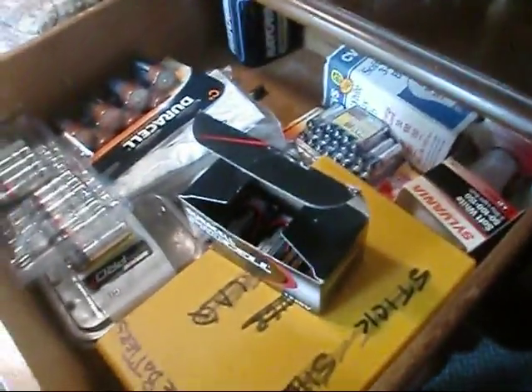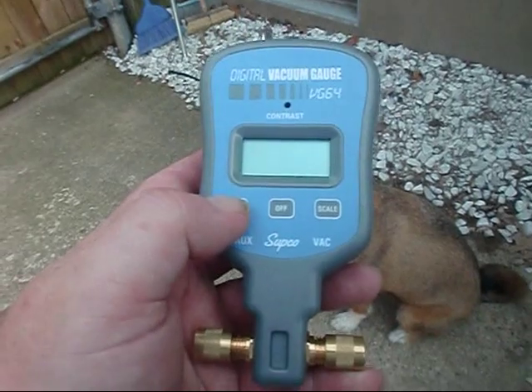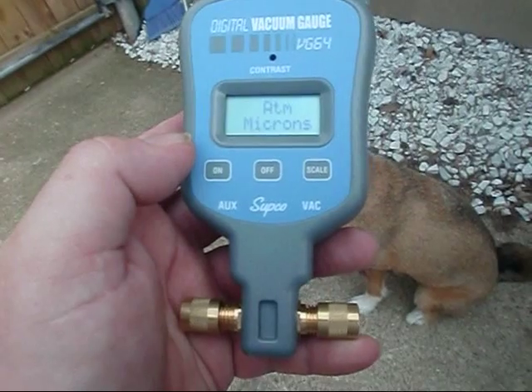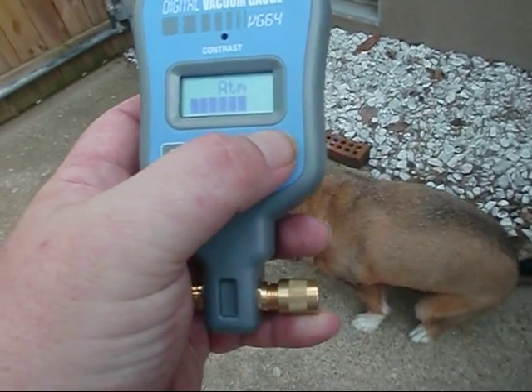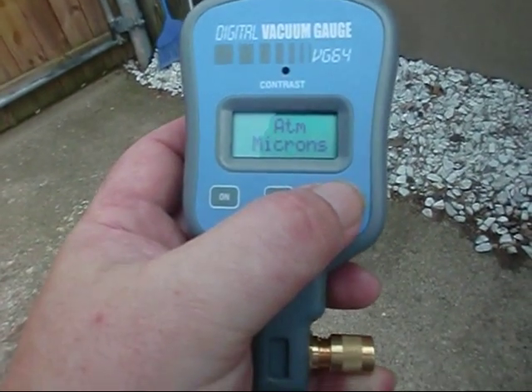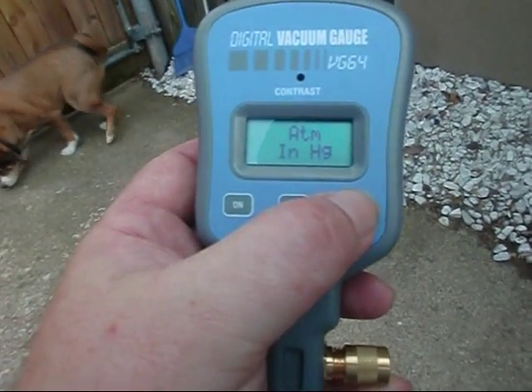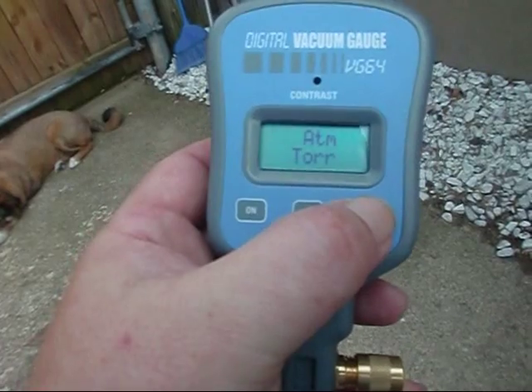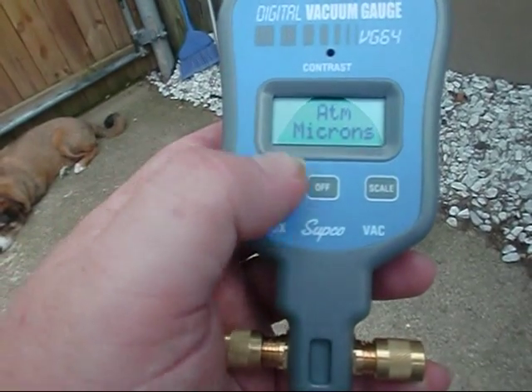For $134 you'd think they'd put a battery in there — oh well. We've got the Supco digital vacuum gauge uncrated. Hold it on there for three seconds and it should illuminate. This is the Supco VG64. ATM is microns, and you can go over to the scale — there's your microns, PSIA, inches of water column, millibars, Pascals, Torr, millitorr, and microns. That's what we'll be utilizing.